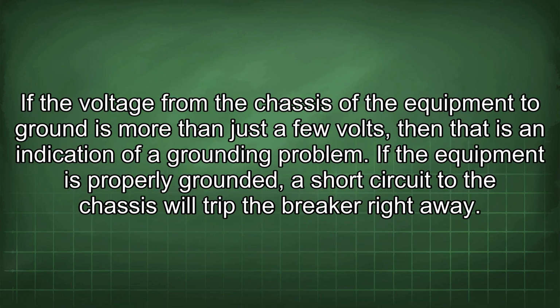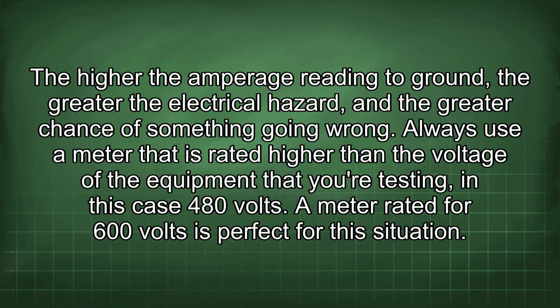If the voltage from the chassis of the equipment to ground is more than just a few volts, then that is an indication of a grounding problem. If the equipment is properly grounded, a short circuit to the chassis will trip the breaker right away. The higher the amperage reading to ground, the greater the electrical hazard, and the greater chance of something going wrong.